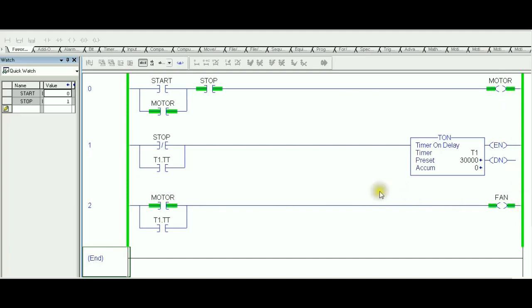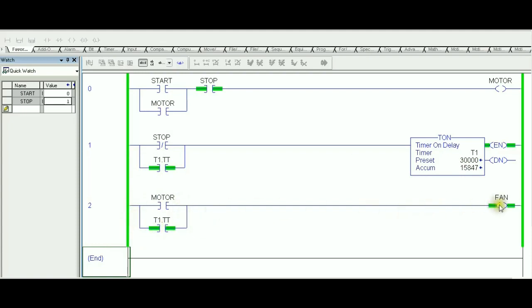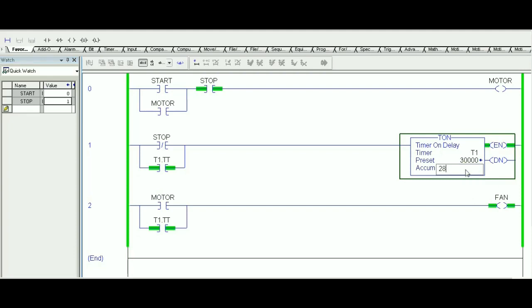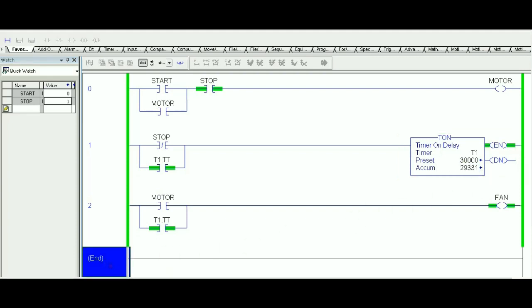When we hit Stop and let go, the timer is triggered and runs for 30 seconds. The latch maintains the timer on even after releasing Stop, and the Timer1.TT contact keeps the fan on as well. After 30 seconds, the timer times out, the latch resets, and the fan turns off. So the same requirements are fulfilled using TON. Whether you use TOF or TON, it's your call — let's keep going.